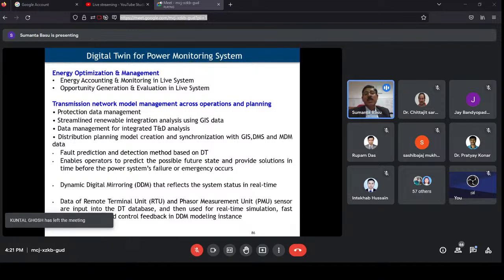Fault prediction and detection method based on the digital twin model. It enables the operators to predict the possible future state and provide solutions in time before the power system's failure or emergency occurs. That is the beauty of this digital twin. Dynamic digital mirroring is another feature. It reflects the system status in real time, and data of remote terminal units and phasor measurement units, or we call it PMU and RTU combinations, and advanced sensors get integrated with the digital twin database and are then used for real-time prediction, simulation prediction, and fast system analysis, and give the management feedback for taking control before some event or disturbance happens in a smart grid system.